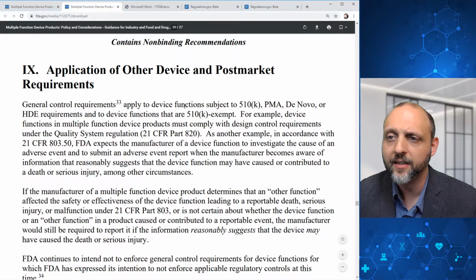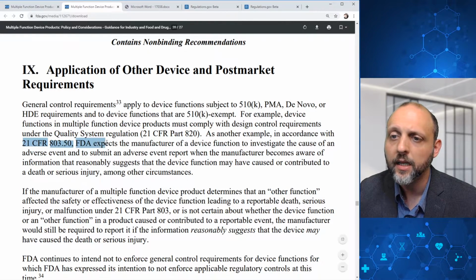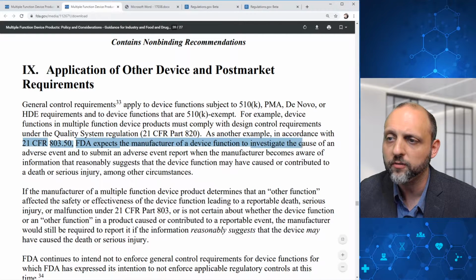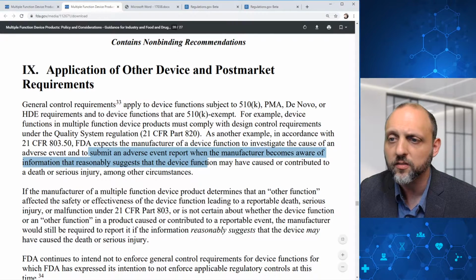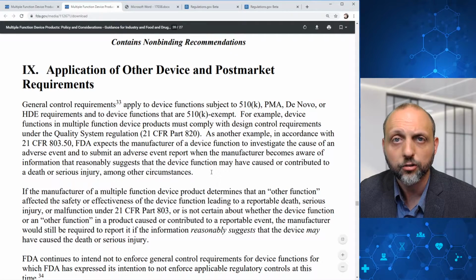General control requirements apply to device functions subject to 510(k), PMA, de novo, or HDE requirements, and to device functions that are 510(k) exempt. For example, device functions in multiple function device products must comply with design control requirements under the Quality System Regulation, 21 CFR Part 820. As another example, in accordance with 21 CFR 803.50, FDA expects the manufacturer of a device function to investigate the cause of an adverse event and to submit an adverse event report when the manufacturer becomes aware of information that reasonably suggests that the device function may have caused or contributed to a death or serious injury, among other circumstances.